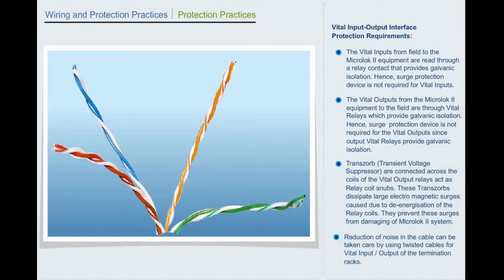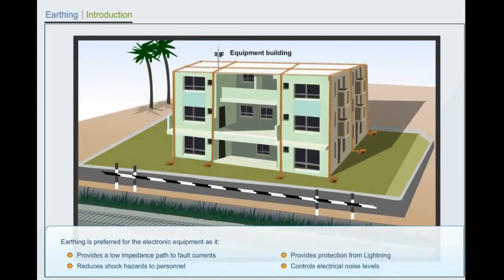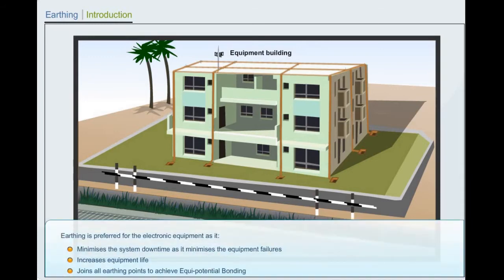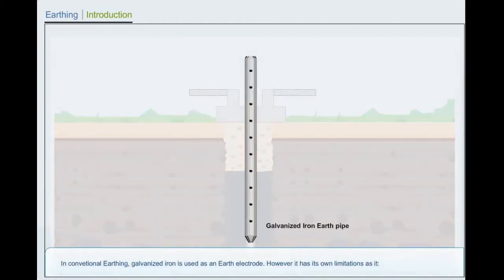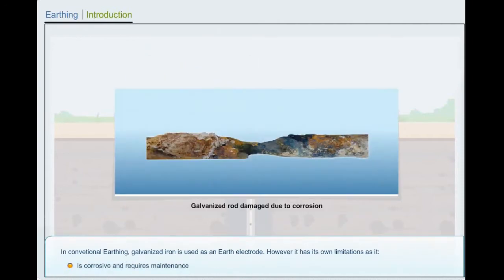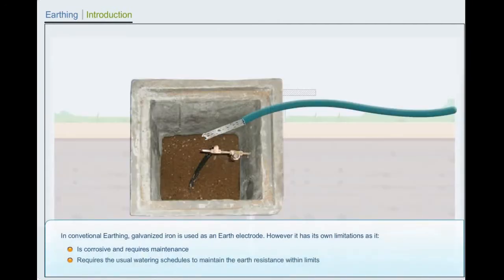Earthing. Introduction. Earthing is preferred for electronic equipment as it provides a low impedance path to fault currents, reduces shock hazards to personnel, provides protection from lightning, controls electrical noise levels, minimizes system downtime as it minimizes equipment failures, increases equipment life, and joins all earthing points to achieve equipotential bonding. In conventional earthing, galvanized iron is used as an earth electrode. However, it has its own limitations as it is corrosive and requires maintenance. It requires the usual watering schedules to maintain the earth resistance within limits.